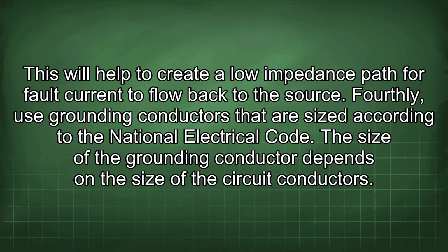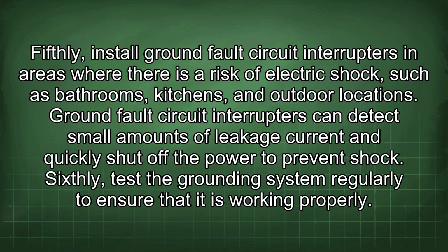Fourthly, use grounding conductors that are sized according to the National Electrical Code. The size of the grounding conductor depends on the size of the circuit conductors. Fifthly, install ground fault circuit interrupters in areas where there is a risk of electric shock, such as bathrooms, kitchens, and outdoor locations. Ground fault circuit interrupters can detect small amounts of leakage current and quickly shut off the power to prevent shock.